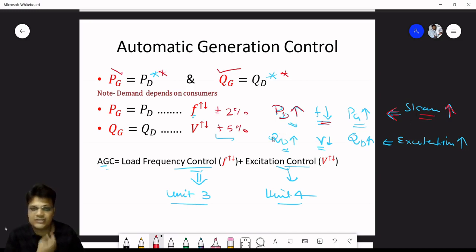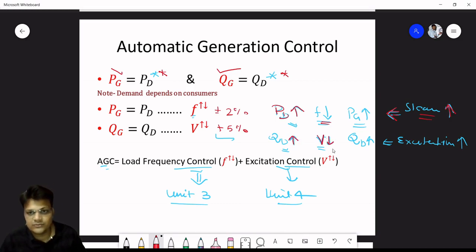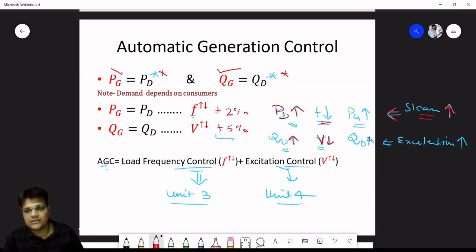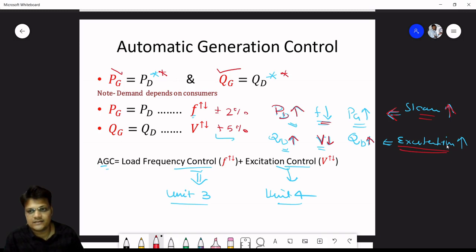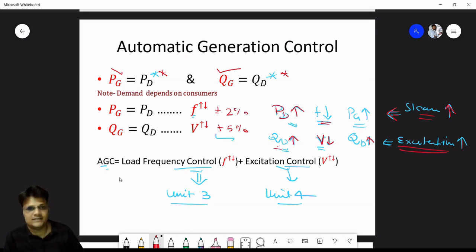Similarly for reactive power demand: when demand increases there is a voltage drop. To reduce the voltage error to within the prescribed limit, we increase reactive power generation by increasing excitation. When excitation increases, reactive power generation increases and meets the increased reactive power demand.